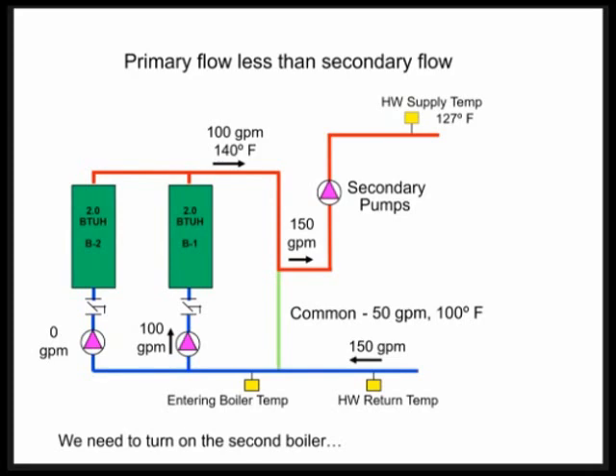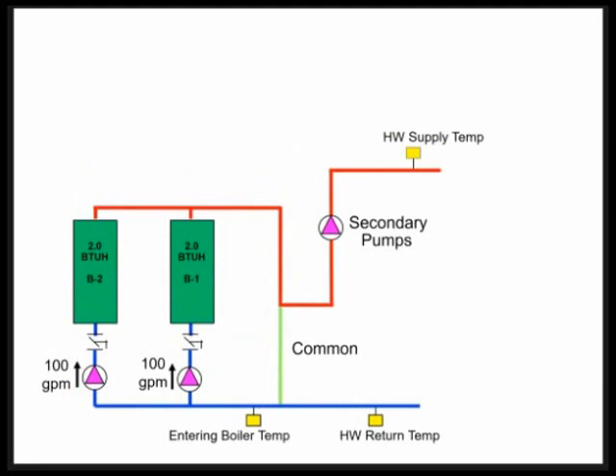This is also why in primary secondary, we like to see our boilers looking at the secondary loop supply, this 127 degrees area right here, so that we know when it's time to bring on another boiler. When the secondary flow is greater than the primary flow, the supply water temperature will drop. So we don't typically operate there. That just tells us we need to turn on that second boiler.